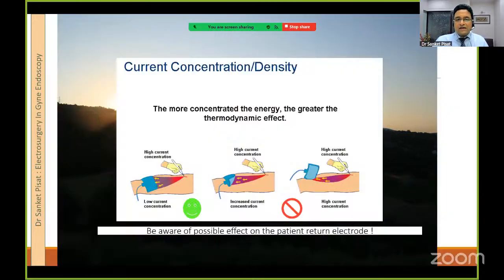Then we come to the second very important concept, which is current concentration and density. Now, we all know that when current enters the body, it causes coagulation. But when current leaves the body, it does not coagulate at the return electrode position.